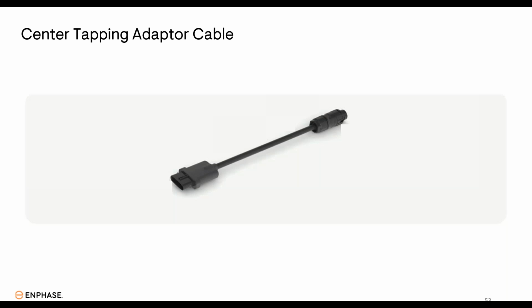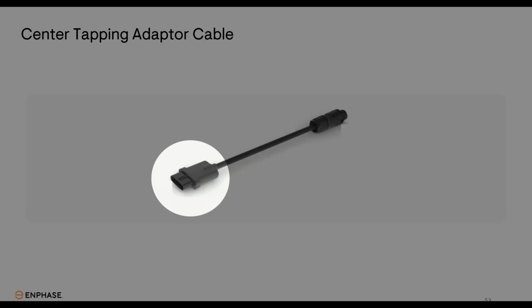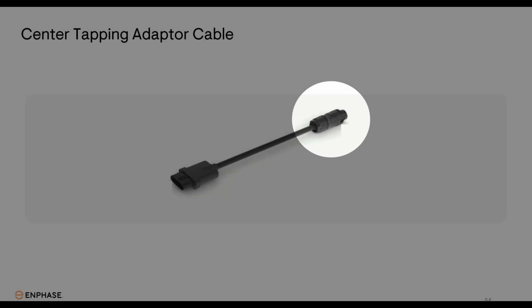The center tap adapter cable, like I mentioned, is very important to reduce that voltage rise, and it is required to be used on any circuit that has more than 6 IQ8P 3P microinverters. On one side, it has a 4-pole link connector, which will plug directly into that center tap connector on the QD cable. The other side has a female field wireable connector. So all you would have to do is make up a male field wireable connector on some raw QD cable, plug it right into that connection, and then you can take that power over to your sub panel board or a junction box to then transition over to whatever wire and conduit that you might need.